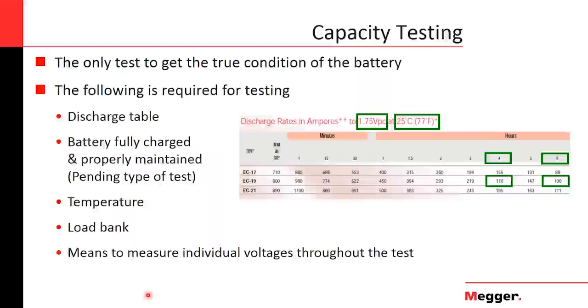For capacity testing, you need four things, or you need the following information. You need the discharge table to be able to get the minimum voltage that you can run the battery to, and there are going to be cases in which you have several minimum voltages for deeper or shallower discharges. You have the temperature. As I mentioned before, temperature is critical for batteries. They should always remain close to this reference temperature indicated in the table of the manufacturer. And then you have the discharge rates.